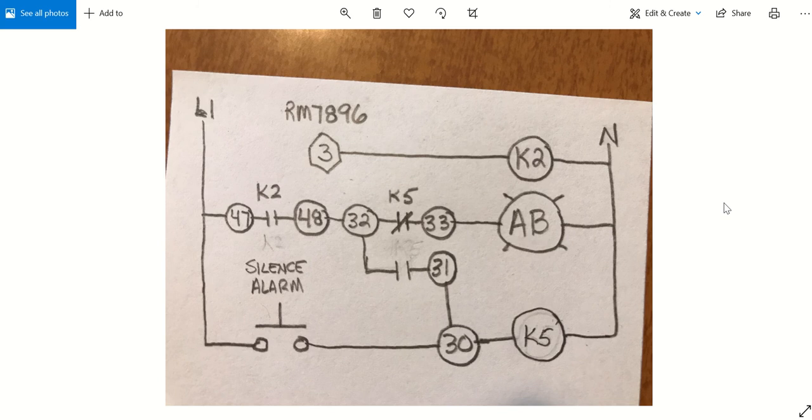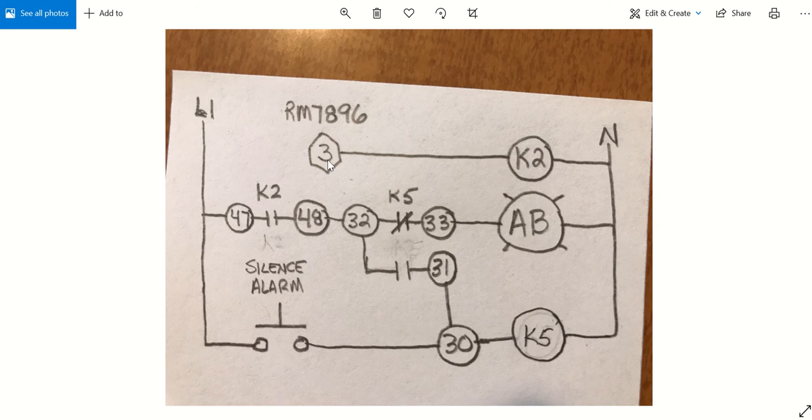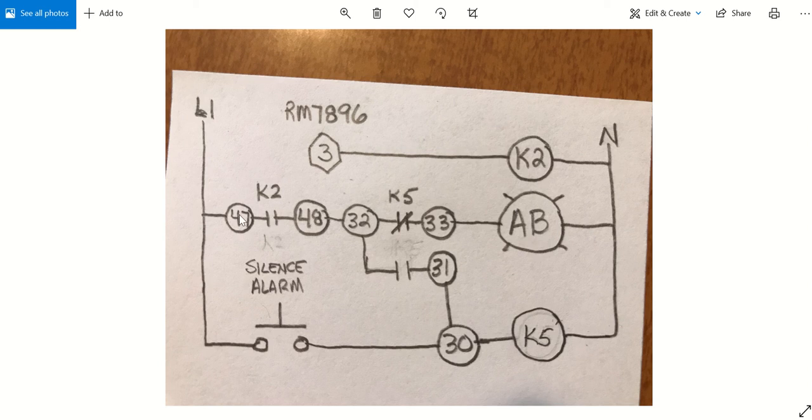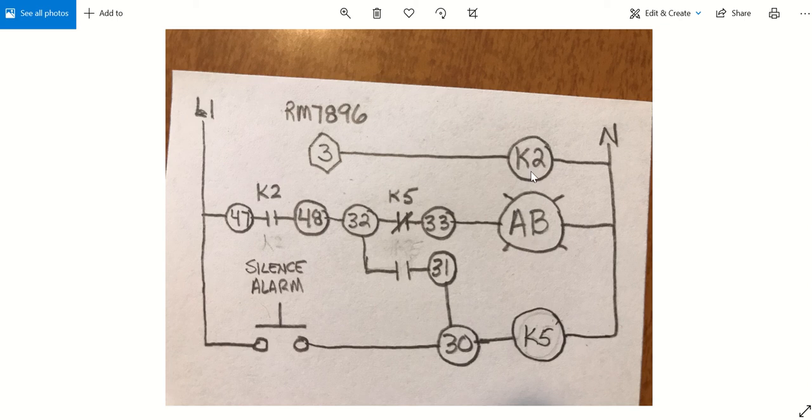Here is terminal number three of the RM7896. This is the alarm terminal. You get 120 volt power right here anytime the flame safeguard's in alarm and it energizes relay K2. Here's the contacts for K2. There's power coming to terminal 47 on one side of the K2 relay contact. Power leaves on terminal 48. It goes with a jumper from 48 to 32. If K5 relay is not energized, this contact right here is closed. Power goes out on 33 and here's the alarm bell. So anytime K2 energizes, this goes closed, power goes straight through it. The alarm bell rings.